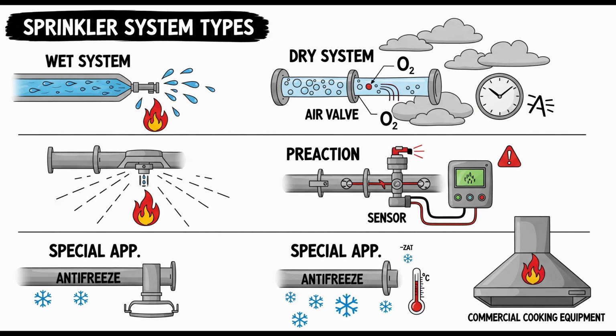Now, a really detailed area in the standard is the size of dry pipe systems. This gets complex because the size directly impacts that water delivery time, which needs to be managed. Right, the delay. You mentioned a 60-second rule earlier for water delivery. Is that the main constraint? That's one option, yes. The system must deliver water to a specified test connection in no more than 60 seconds from the time the test connection is fully opened and the system starts at normal air pressure. Okay, 60 seconds to the test point. But there are other ways to comply, often tied to system volume, the total amount of air in the pipes.